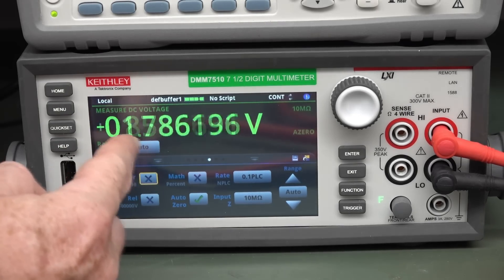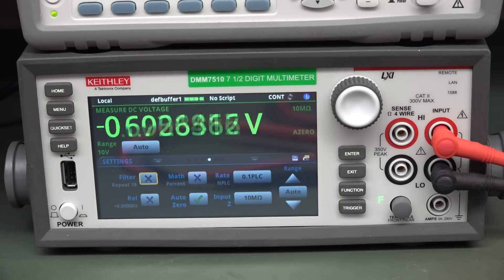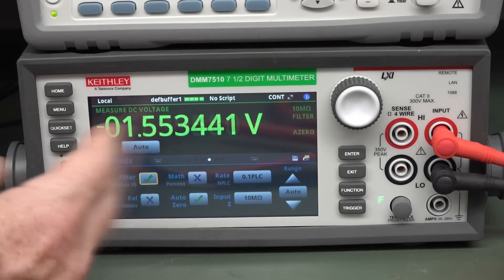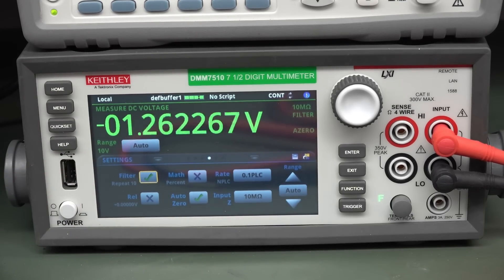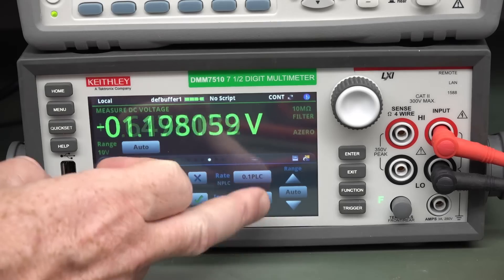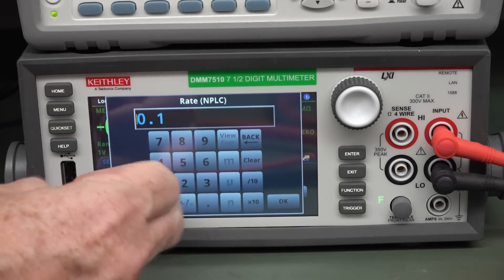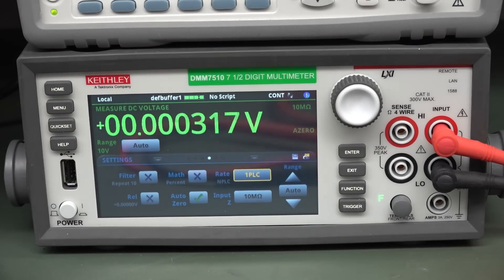And you can get the meter to do weird auto-ranging stuff we saw on that Philips one. And the Keithley one down here, exactly the same thing. Like, I've got the smoothing filter actually on. Right? The smoothing filter doesn't do anything. It doesn't help your cause at all. And check it out. It's just going, meh, auto-range. In there, oh, look, it's even going 10 volts, 1 volt. Right? It just doesn't know what to do. It's just absolutely nuts. And you turn on the smoothing filter and, well, it's still, it's a little bit slower, of course, but those high voltages are still there. It's not getting rid of them. And once again, we're still 10 megohms input impedance. But you'll see that we're 0.1 power line cycles. So, I'll turn off the filter here, and we'll change that to one power line cycle. Bingo! It's gone away. Because we're doing at least an integration over one full 50 or 60 hertz power line cycle. Nice!